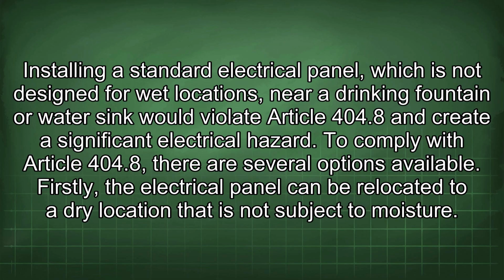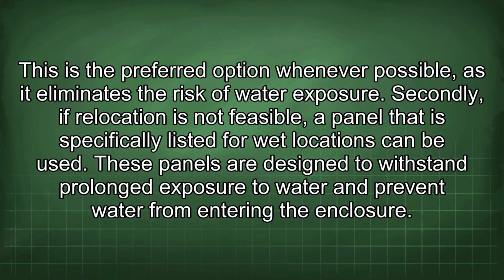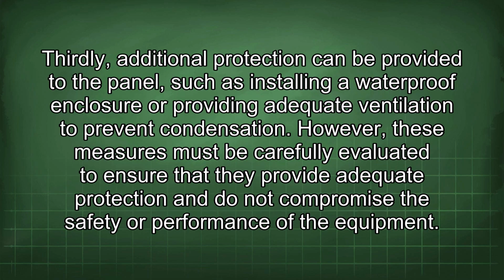To comply with Article 404.8, there are several options available. Firstly, the electrical panel can be relocated to a dry location that is not subject to moisture. This is the preferred option whenever possible, as it eliminates the risk of water exposure. Secondly, if relocation is not feasible, a panel that is specifically listed for wet locations can be used. These panels are designed to withstand prolonged exposure to water and prevent water from entering the enclosure. Thirdly, additional protection can be provided to the panel, such as installing a waterproof enclosure or providing adequate ventilation to prevent condensation. However, these measures must be carefully evaluated to ensure that they provide adequate protection and do not compromise the safety or performance of the equipment.